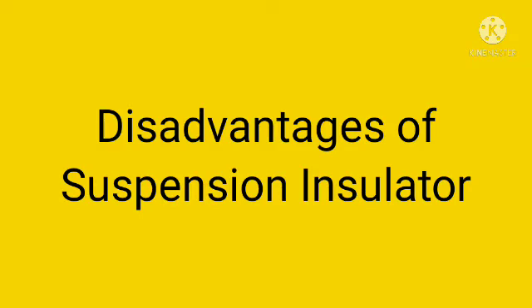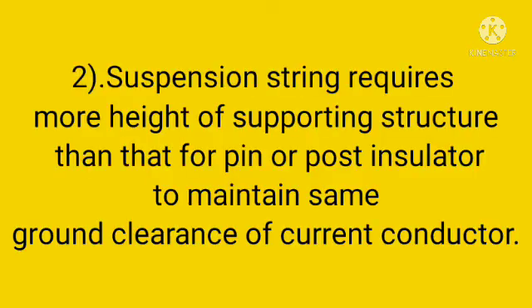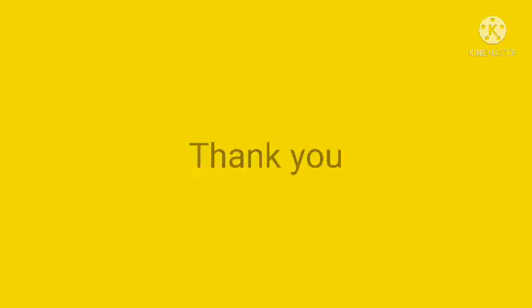Disadvantages of suspension insulators: a suspension insulator string is costlier than pin and post type insulators. Suspension strings require more height of supporting structure than pin or post insulators to maintain the same ground clearance. Also, the amplitude of free swing of conductors is larger in a suspension insulator system, so more spacing between conductors must be provided.